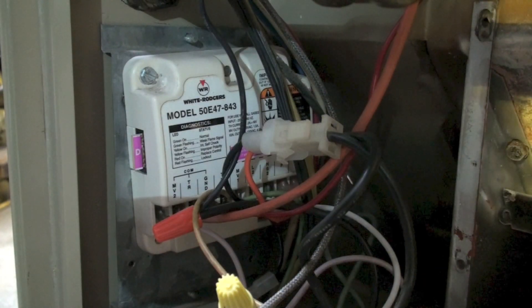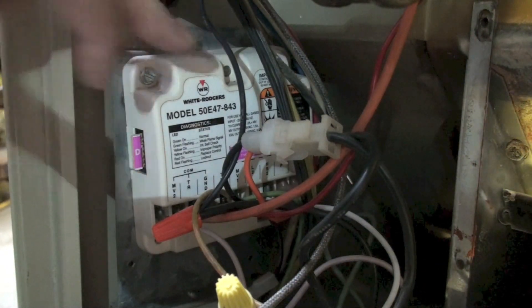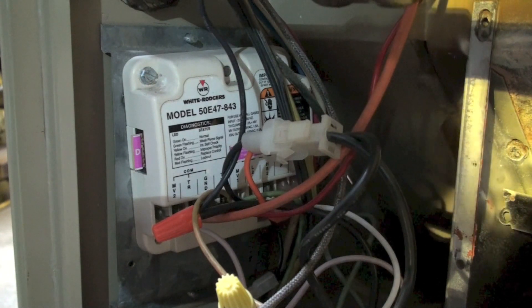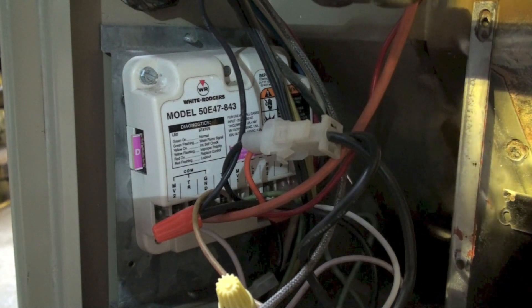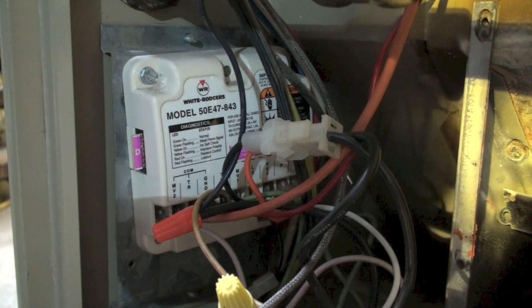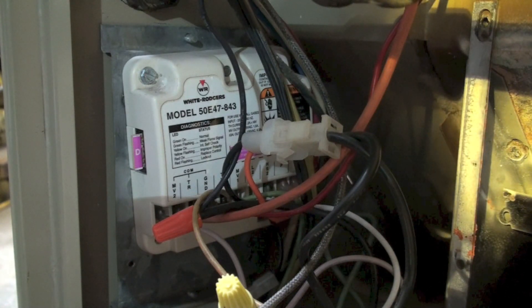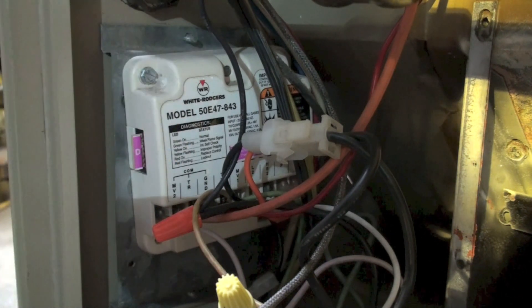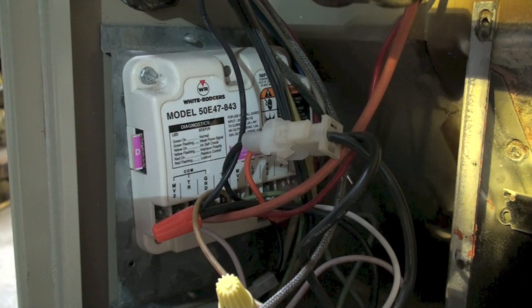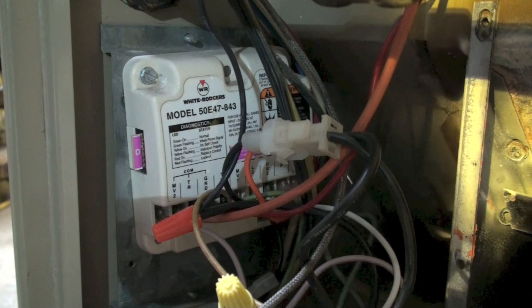However, when I look at my control, there's no light at all. And if I put a meter on the control for this thermostat, also no power. So the ignition module does not appear to be showing any power.